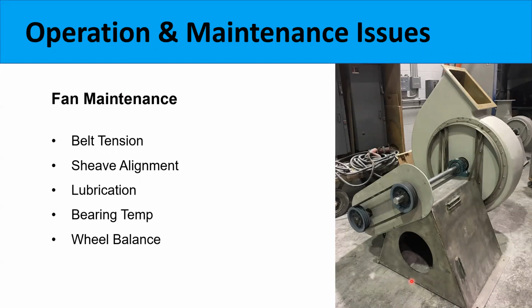Exhaust fans and blowers are a very critical part of the system that needs to be maintained. Some common issues that we see in the field revolve around belt tension maintenance, sheave alignment, where these sheaves aren't aligned, or bearing temperature, vibration, wheel vibration. Those are really some of the most common issues that we see with fans in the field. So it's important to keep a regular maintenance on these fans.